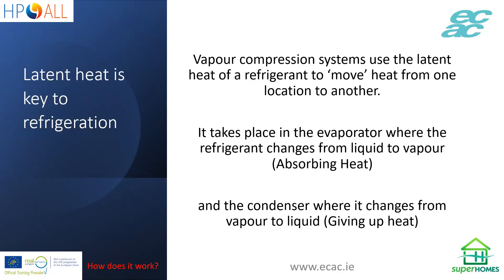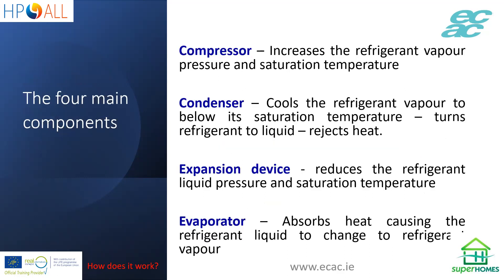The whole thing is based on latent heat and using it to move heat from one location to another. The vapor compression system uses the latent heat of a refrigerant to move heat from one location to another. In the evaporator, we cause a liquid refrigerant to turn into a vapor, and in doing that it absorbs heat. The four components matter an awful lot when we're dealing with energy. The compressor increases the refrigerant vapor pressure and saturation temperature — it's the biggest single energy user on the system.